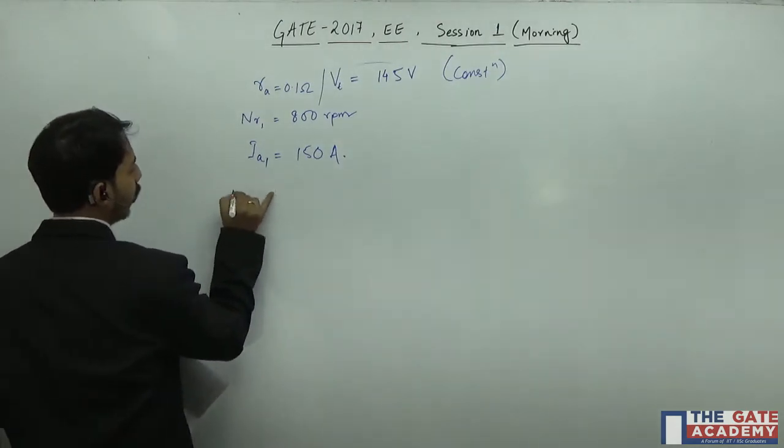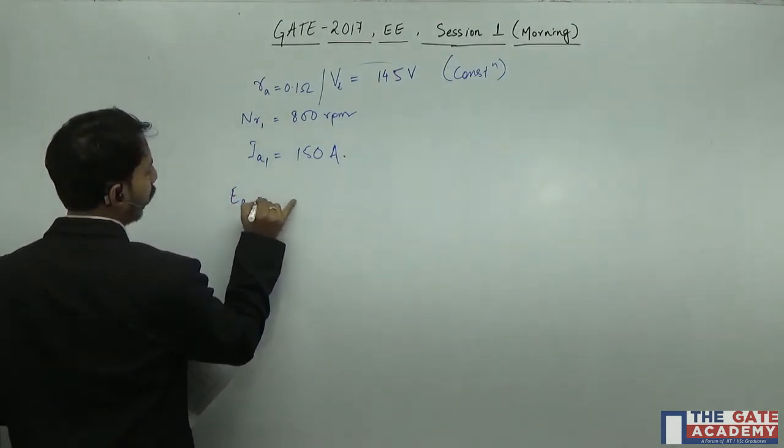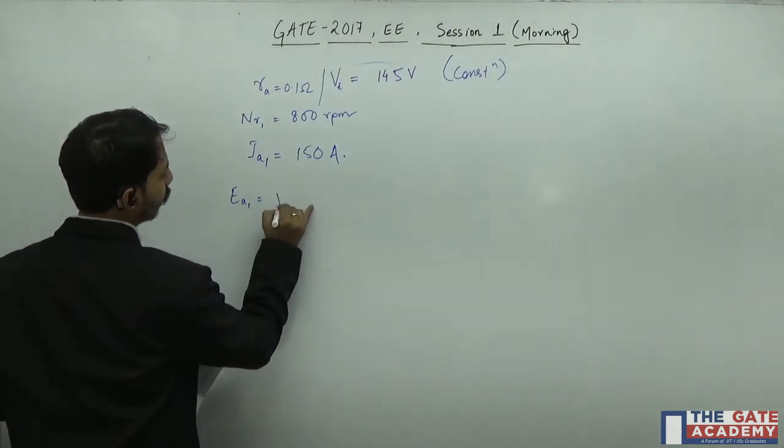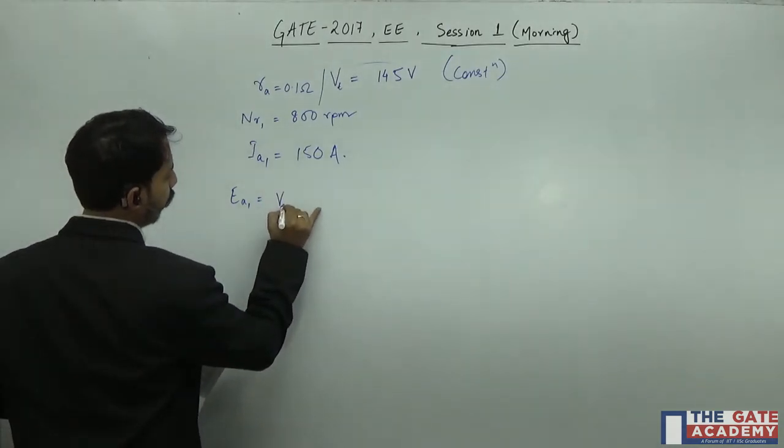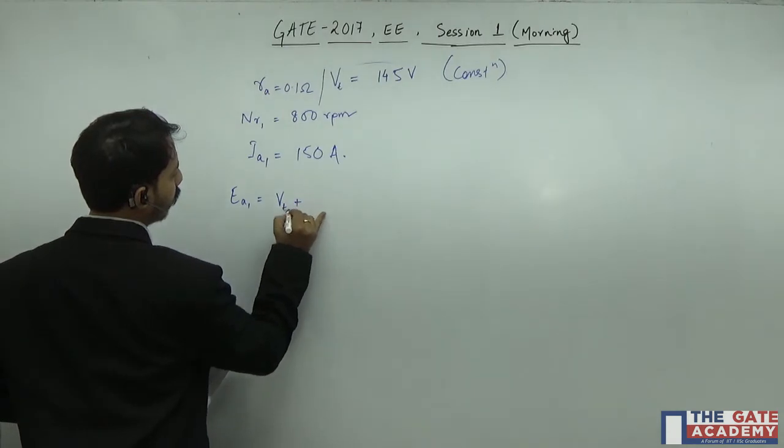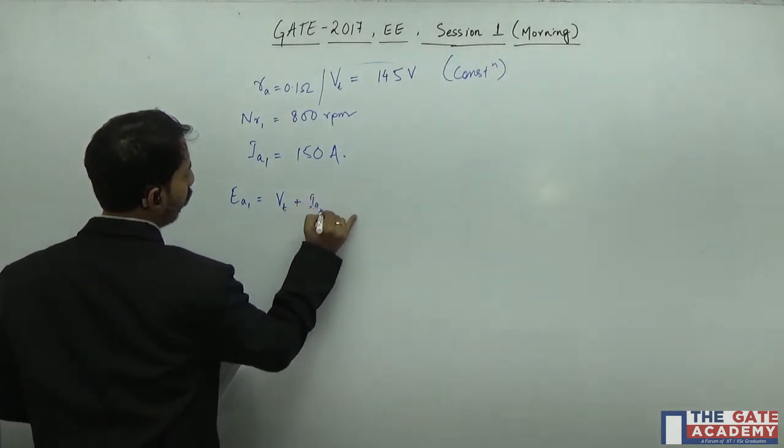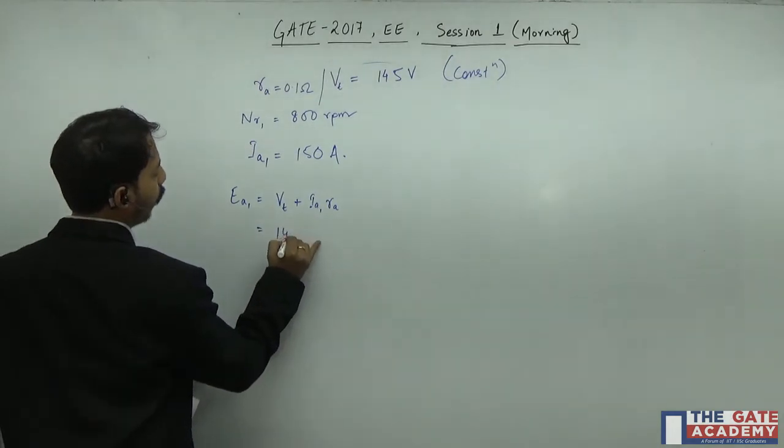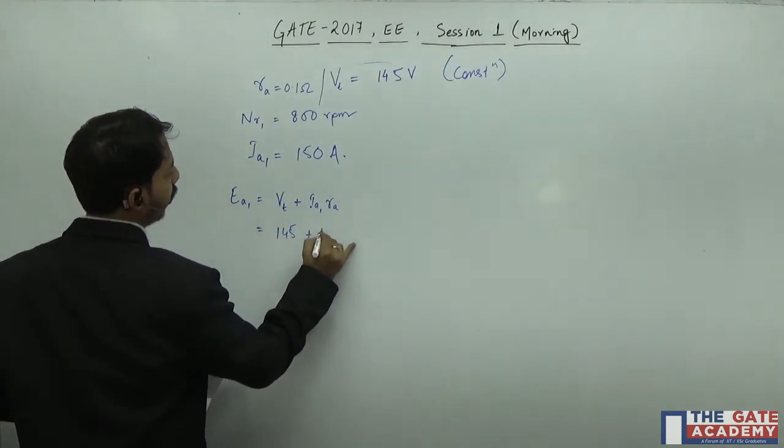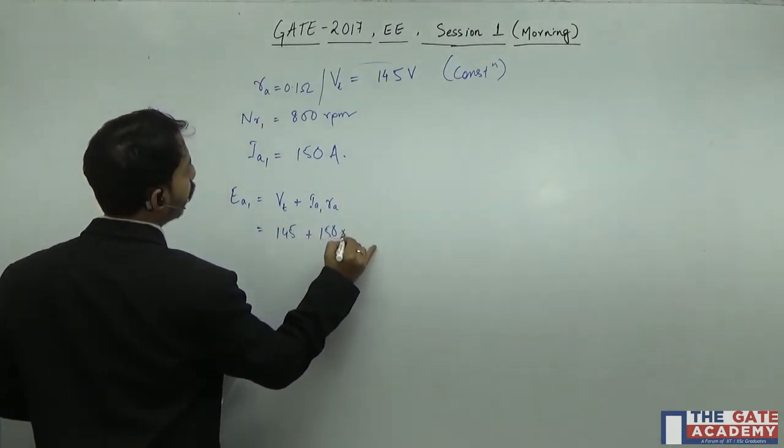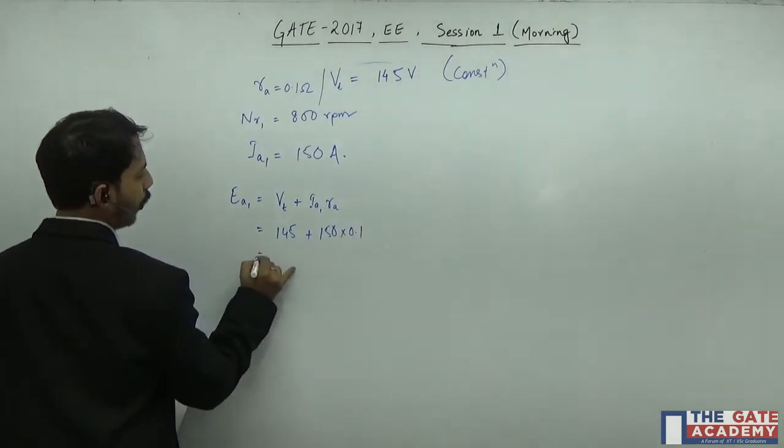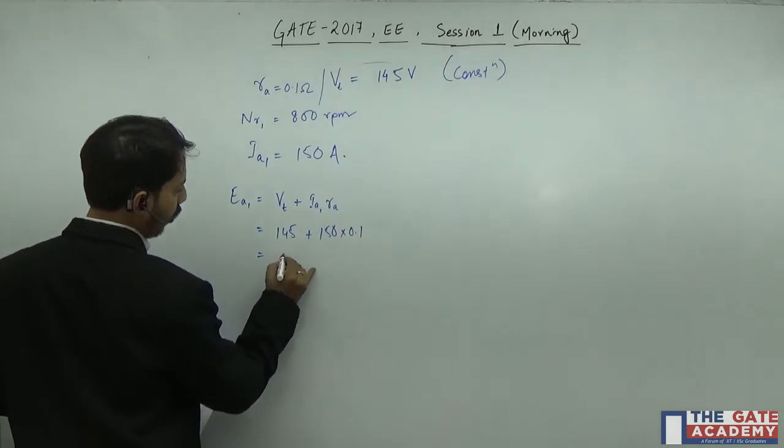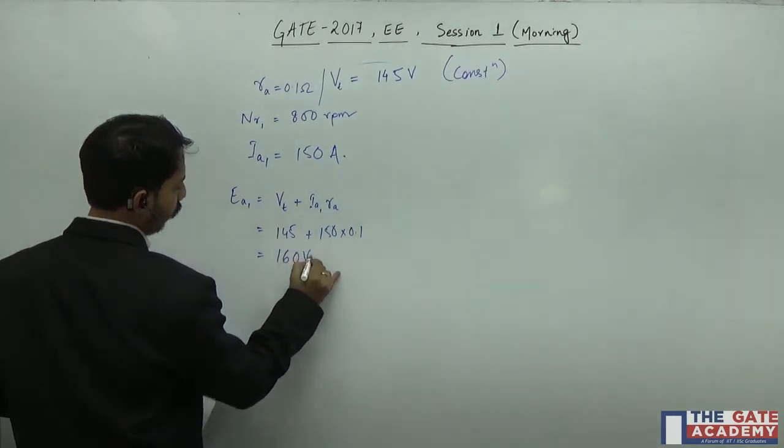In this case we can calculate the EMF. EMF will be VT plus IA1 into RA. VT we know is 145 plus I is 150 into 0.1, so it will be 145 plus 15 equals 160 volts.